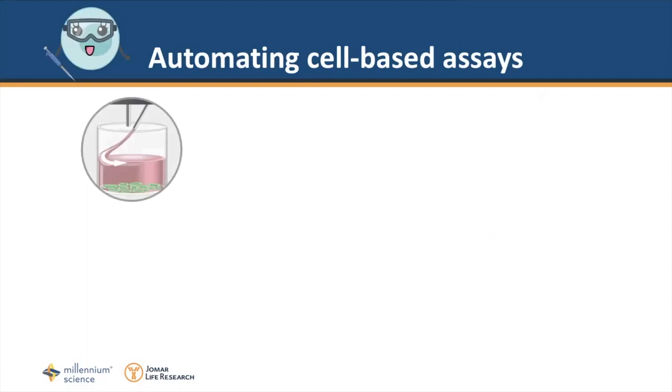The biotech plate washers have two features that permit automation of cell-based assays. The first is angling of dispense tubes and the second is by reducing fluid flow. Angled dispense tubes adjust the fluid path to the side of the wall. Doing so reduces the vortex-like effect that liquid dispensing creates and this can be detrimental to the monolayer integrity.